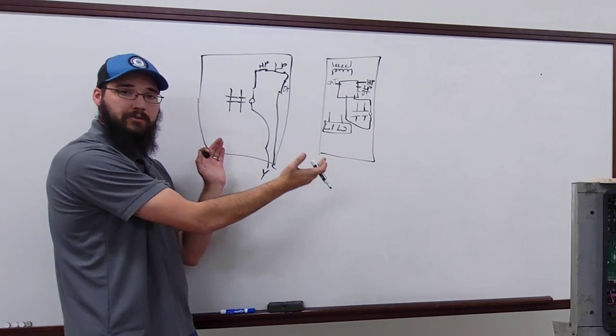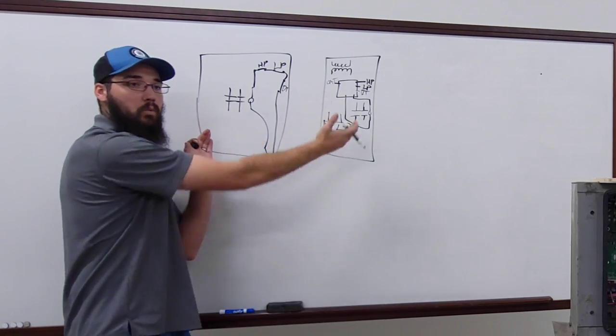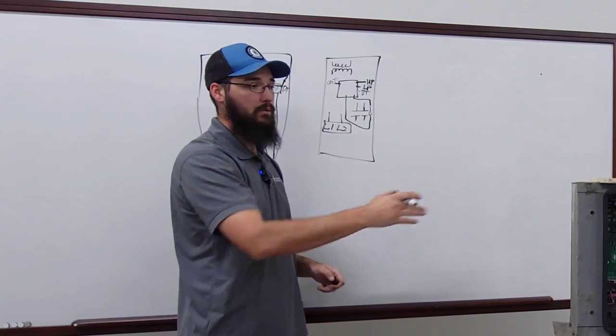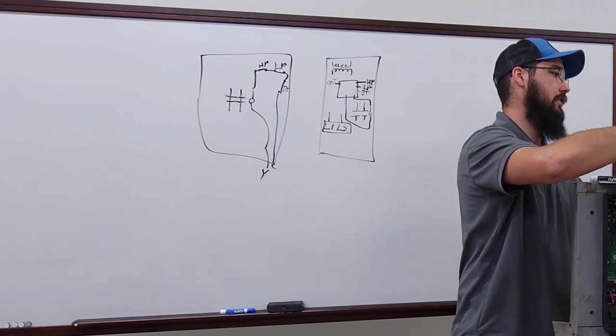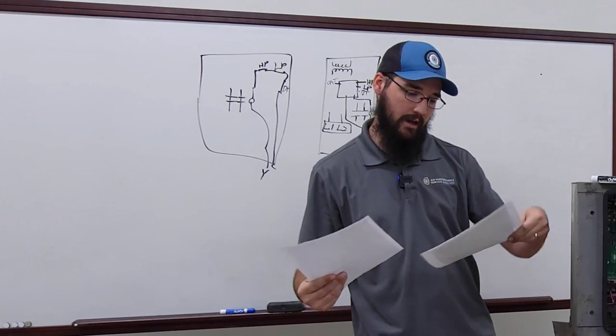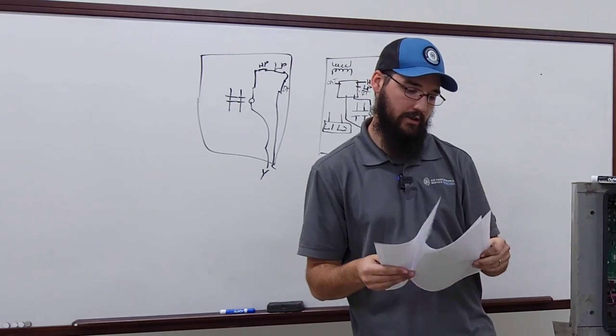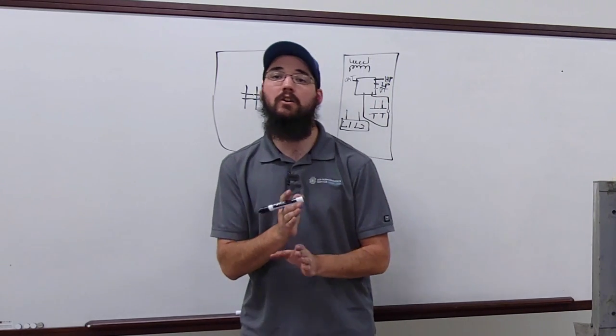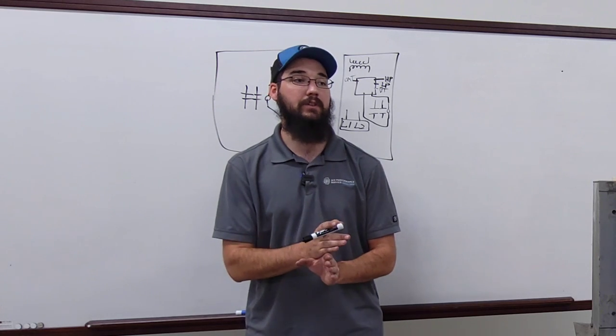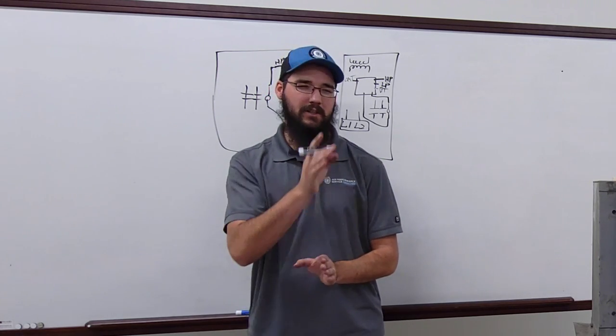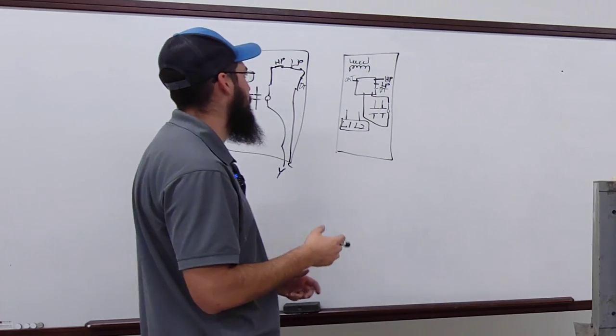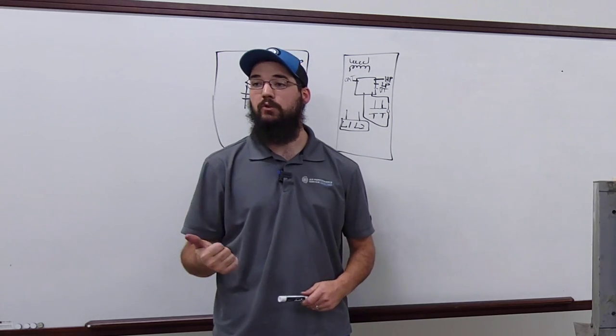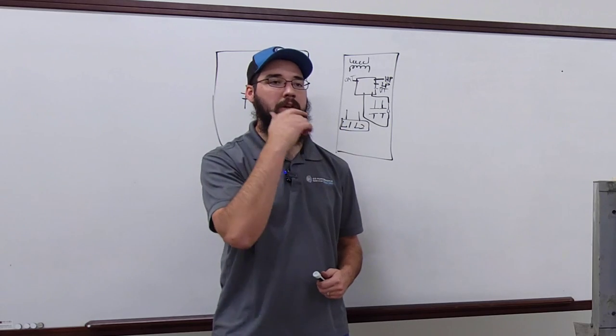This is just a picture of where we're at as an industry and what's changing. As systems grow and develop, we can look at the controls. Some of the things these systems are doing is they are no longer using high and low pressure safety switches — there's not a physical switch anymore. There's no switch to read across and say, is this open or closed? It is quite literally the transducer. The panel is actually using the transducer pressures — whether the low pressure transducer or the high pressure transducer — as the safety.